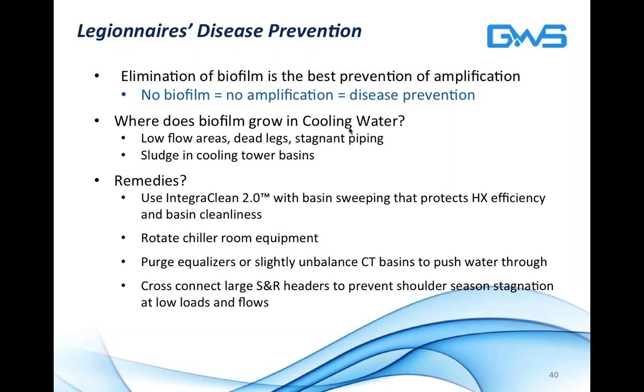The Griswold water system remedy is to use IntegraClean 2.0 with basin sweeping that protects your heat exchanger efficiency and provides basin cleanliness. Rotating chiller room equipment so you don't have stagnant water is very important. As far as dead legs and other stagnant piping, make sure you're purging basin equalizers or slightly unbalancing the cooling tower basins to push water through so it's treated continuously. Often you can cross-connect large supply and return headers to prevent shoulder season stagnation at low loads and low flows.